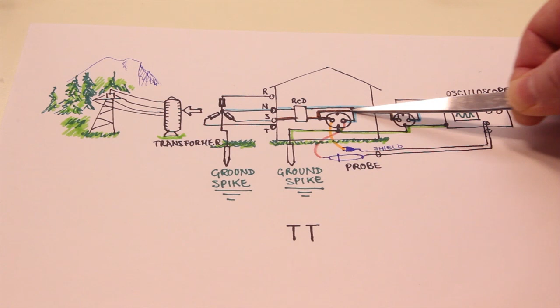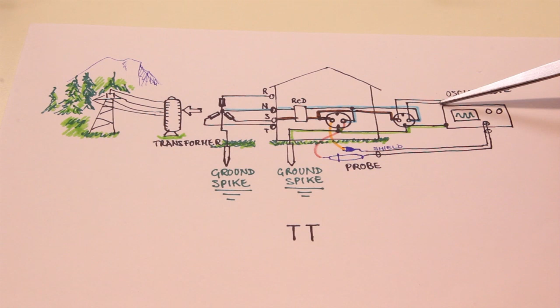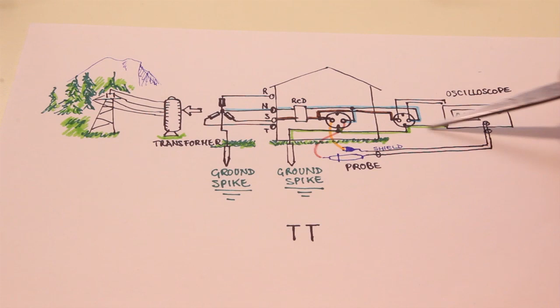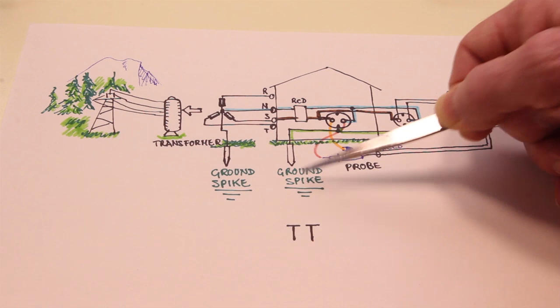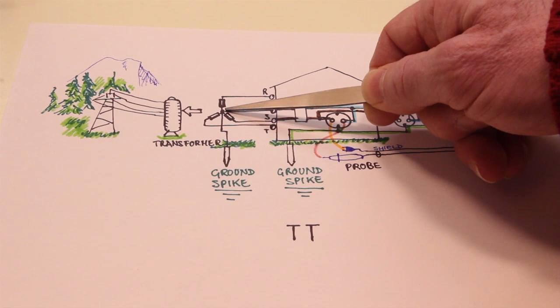The two wires that provide the power go to a transformer, so there's no electrical galvanic connection between this point and the internal power supply of the oscilloscope, but the ground is connected through the socket to the main ground, the spike ground here. So the neutral ends up at the same level as the ground.